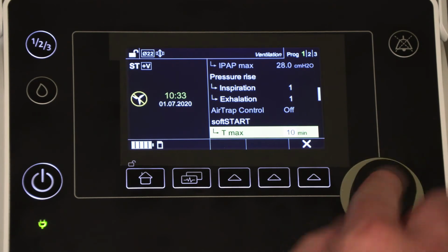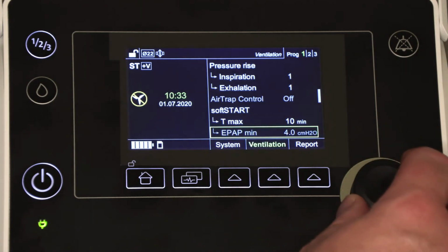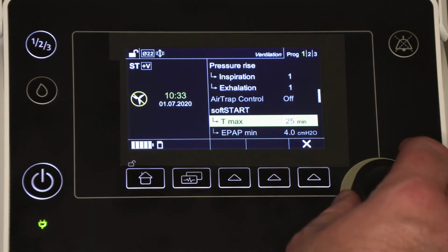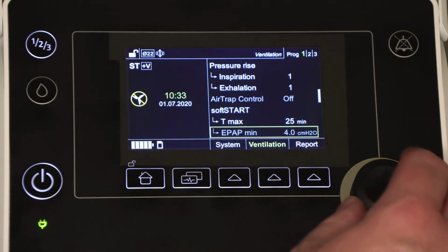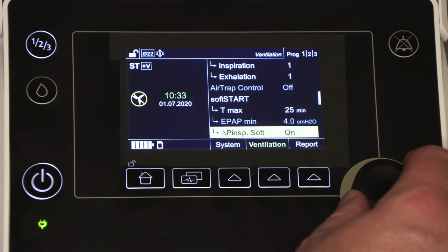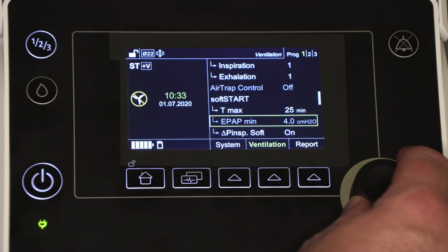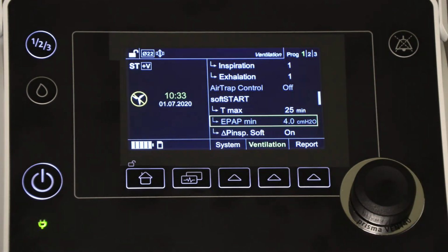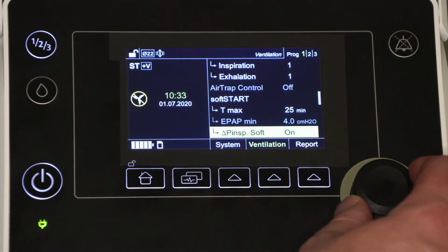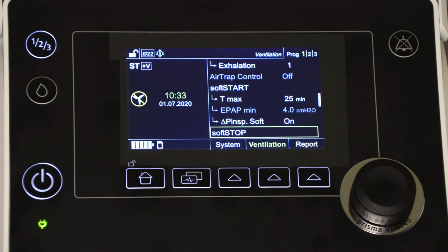You can set a minimum EPAP to be used to start the process. When the PINSP setting is set to on, the starting IPAP will be 2 cm above the current EPAP setting and will climb to the prescribed set IPAP over the period of time set as your soft start Tmax.